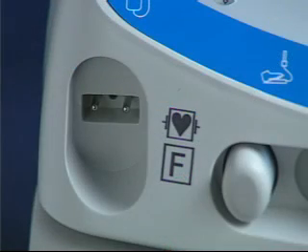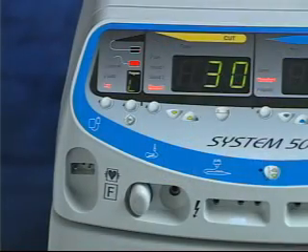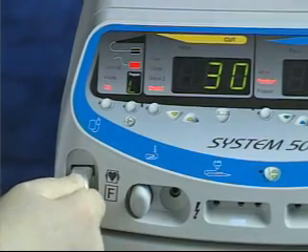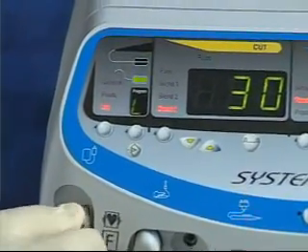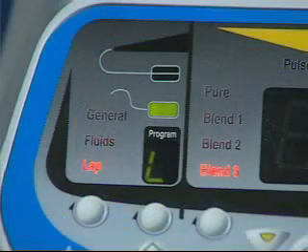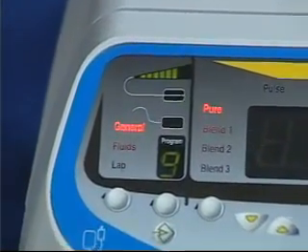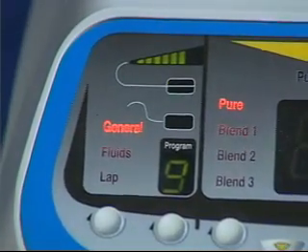Connecting the dispersive electrode is also intuitive. Follow your hospital's guidelines for applying the dispersive electrode to the patient, then plug the connector into the illuminated dispersive electrode portal. The system will automatically sense whether a single or dual-foil dispersive electrode is in use, illuminate the proper icon, and activate the appropriate monitoring system. A dual-foil dispersive electrode will activate ARM — ConMed's Automatic Return Monitoring system.